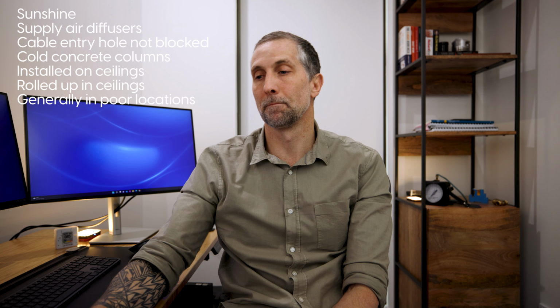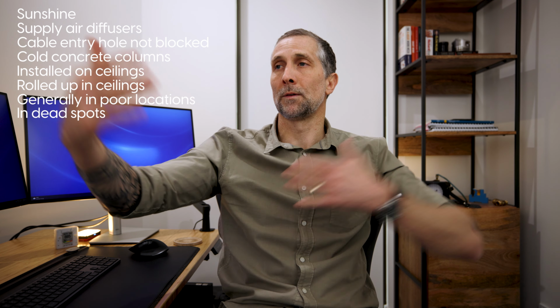It's behind something. The other one that doesn't happen very often, I've noticed, is just a sensor installed in a dead spot in a room. So in my office here, if I had the supply air diffuser in the corner there, and the supply air was blowing through and coming out the return over here, so this was my air change path like this, and the sensor is in that corner of the room over there. Not usually a problem, but I just have had some unique situations where the sensor's not reading quite right and there's temperature complaints because the sensor is not in the return path of the thing.